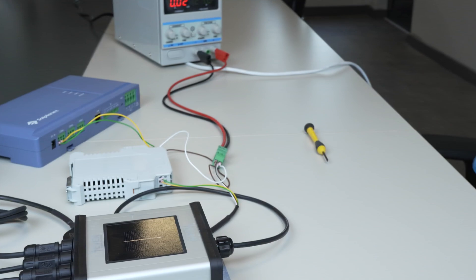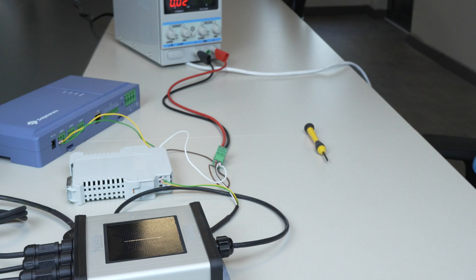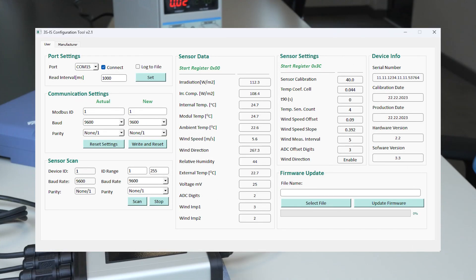In case more than one device is connected to the COM port you have connected the 3S-IS sensor box to, device IDs must be different while baud rate and parity values must be the same. When you want to change the sensor ID, you can change it by using the 3S-IS configuration tool.